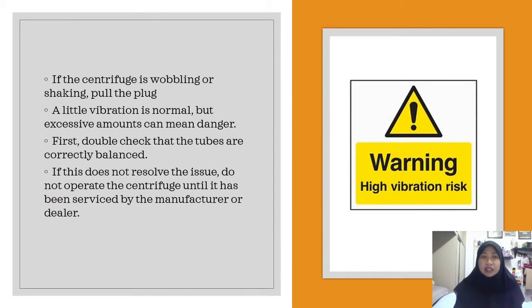If the centrifuge is wobbling or shaking, pull the plug. A little vibration is normal, but an excessive amount can mean danger. First, double-check that the tubes are correctly balanced. If this does not resolve the issue, do not operate the centrifuge until it has been serviced by the manufacturer or the dealer.